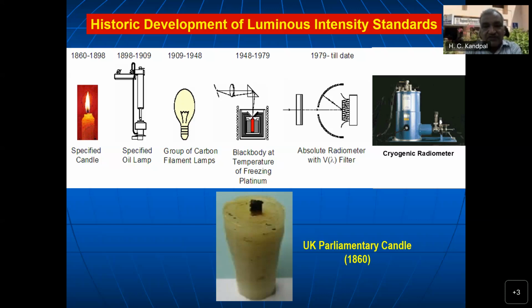It was thought that if we can develop a self-calibrating detector, meaning you do not need any external source to calibrate it, that radiometer is called an absolute radiometer, or later an electrically calibrated radiometer. If we have this radiometer in the labs, it can be used for intercomparison, calibrating silicon photodiodes against it, which will be second generation. Otherwise it will be third, fourth generation intercomparison with the black body, so the uncertainty in measurement will propagate and there will be larger scatter in the values.